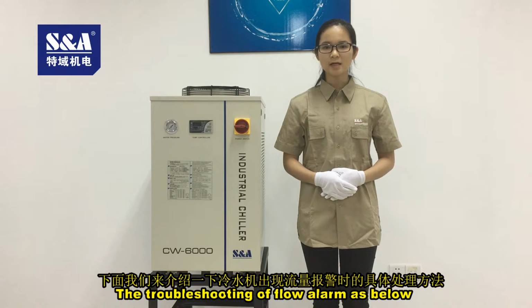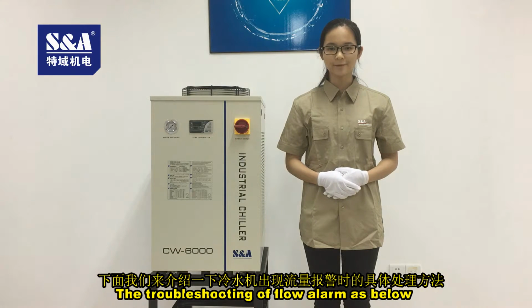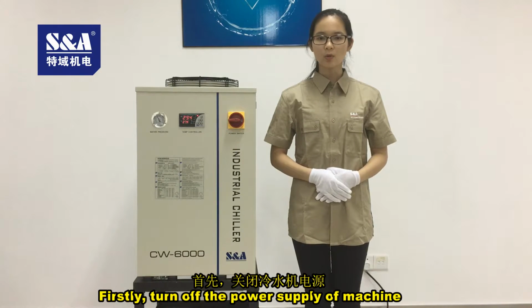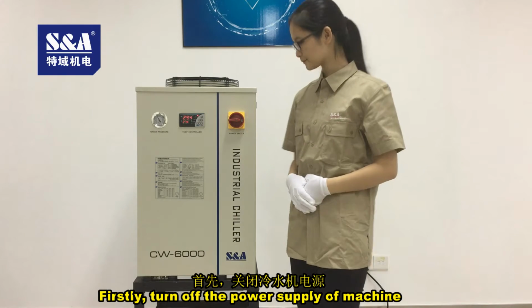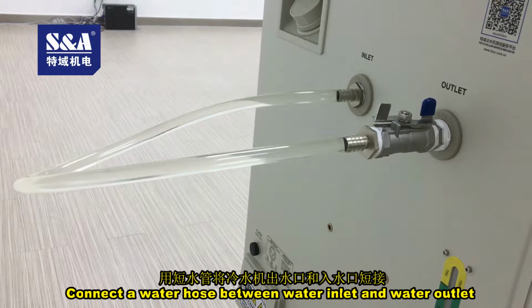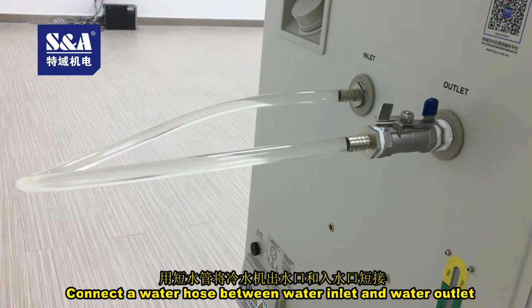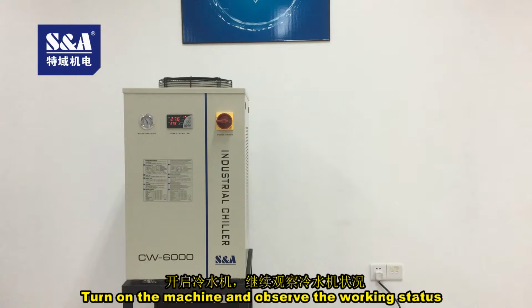The troubleshooting of the flow alarm is as below. Firstly, turn off the power supply of the machine. Connect a water hose between the water inlet and water outlet. Turn on the machine and observe the working status.